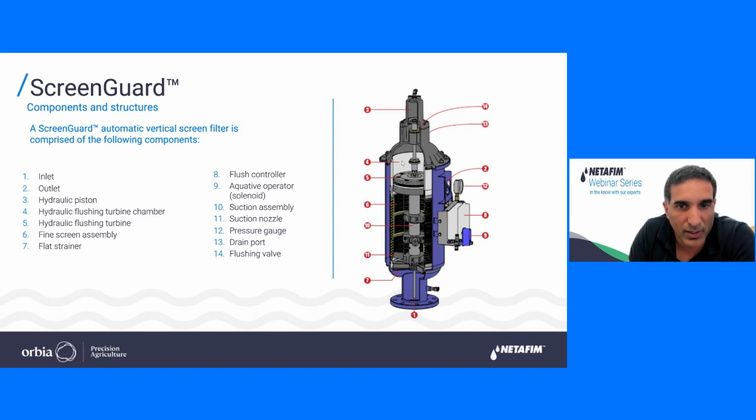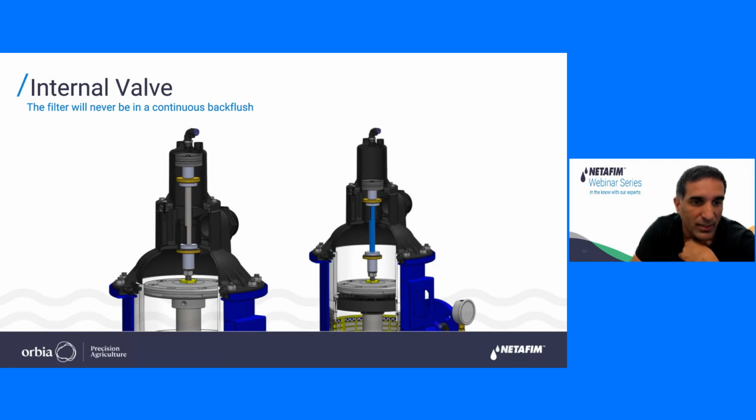Here on the top side of the filter, you can see the backflush mechanism, and this is the feature that I described as one of the important ones for preventing the continuous backflush. So this is the way it works. It operates once there is pressure. It operates the backflush mechanism, and the nozzle starts to work. And once the cycle is over, this internal valve will always go back to the initial position, and the backflush will cease from happening.